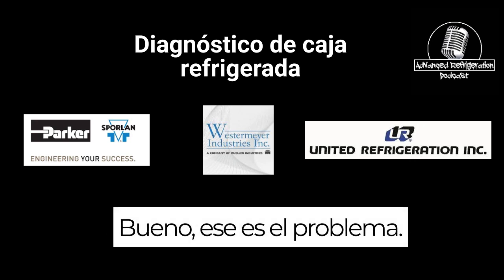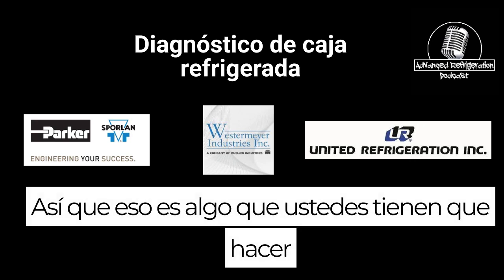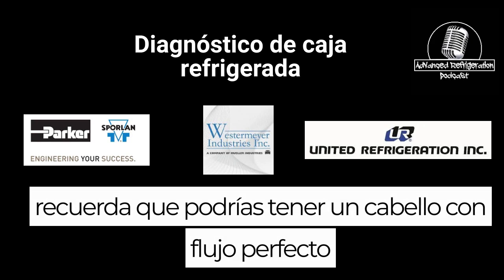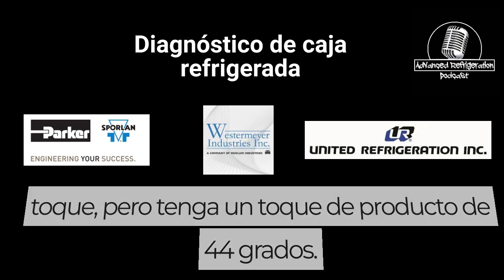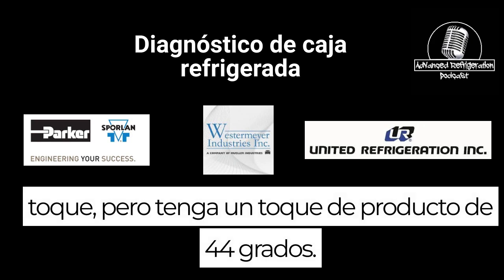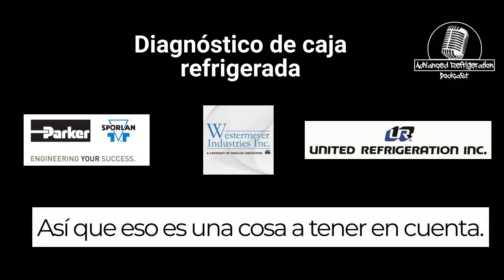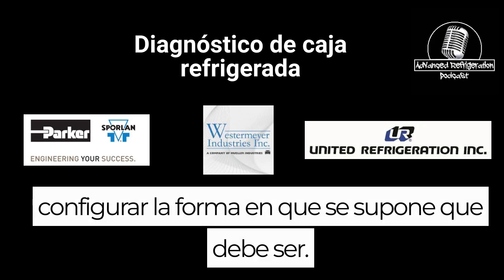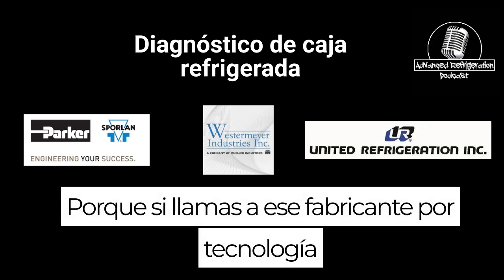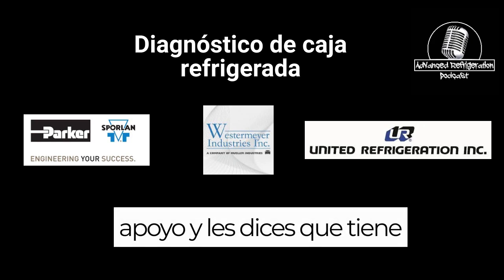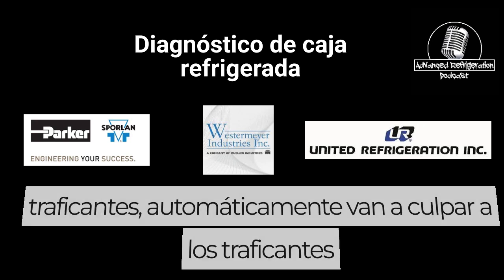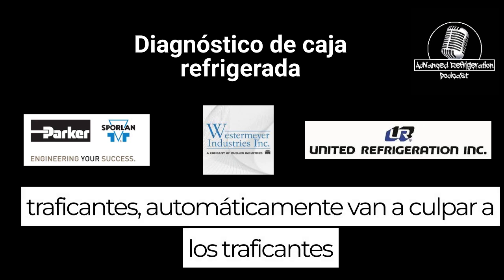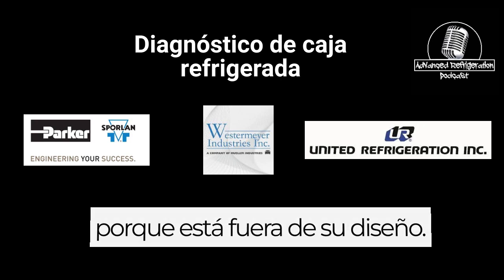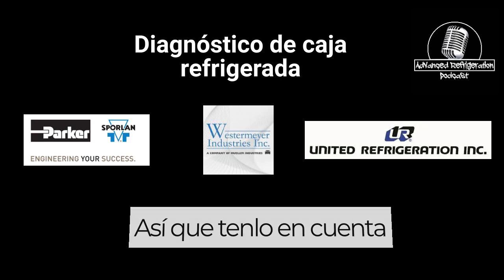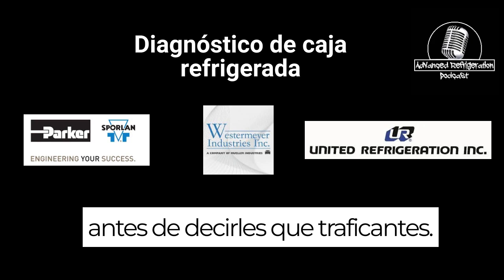Well, that's the issue. So that's one thing you guys have got to remember: you could have perfect discharge air temp, but have 44-degree product temp. So that's one thing to be mindful of. You've got to make sure that case is set up the way it's supposed to be. Because if you call that manufacturer for tech support and tell them it's got pushers, they're automatically going to blame the pushers because it's outside of their design. So just keep that in mind before you tell them that it has pushers.